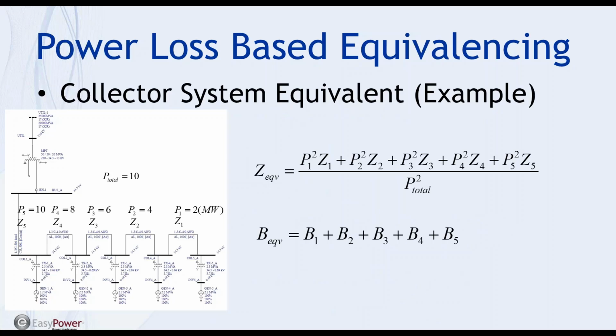Implementation. Let's take a simple example. Using the same one line we used before, I use 2 megawatt, 2.2 MVA inverters, and I have 5 collector circuits to connect each inverter together using a radial connectivity, right? From the low side of my MPT, go 1, 2, 3, 4, 5 levels. Now I have my 5 circuits, and from my farthest circuit, which is circuit 1, I have 2 megawatt. Going one closer to the substation transformer, I have 4 megawatt, 6, 8, 10.